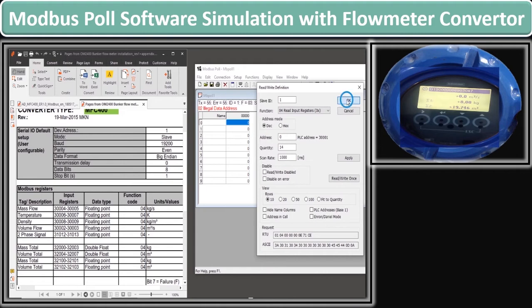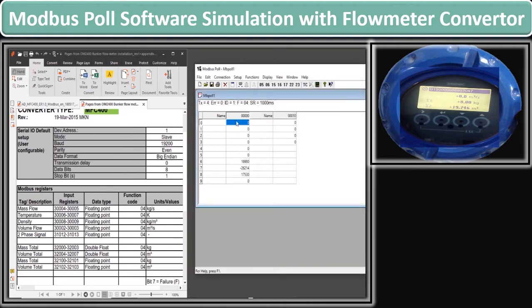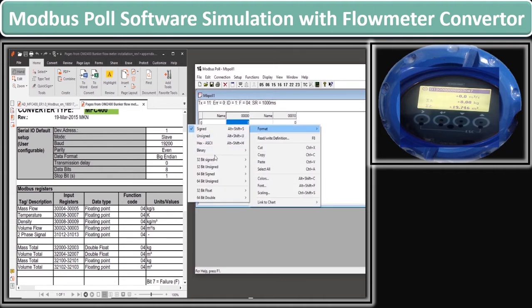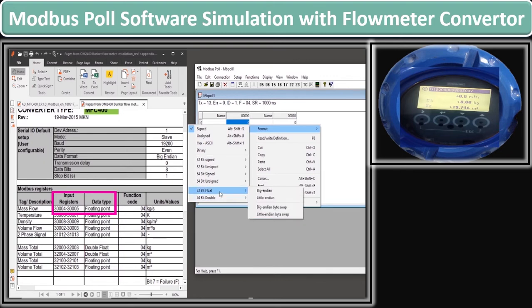Click OK. You see that some raw values start coming on the screen. You now have to set the data type and data formatting of the raw values to get the exact Modbus values of the flow meter. Right-click on the first value — the first option given is Format. When you click on Format, you get many data type options. As stated in the parameter list, the data type is floating point and two registers are used for each value. So we go to 32-bit Float. When we select 32-bit Float, we get the option of data formatting. As mentioned in the parameter list, the data format is Big-Endian, so we select the Big-Endian option.